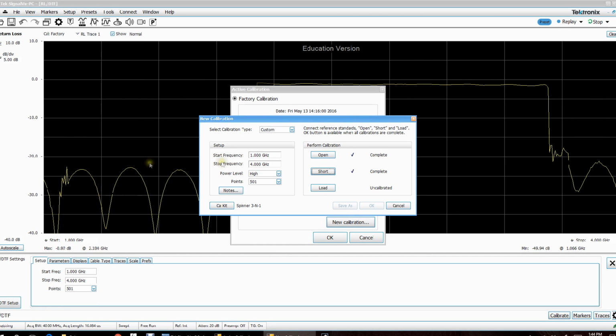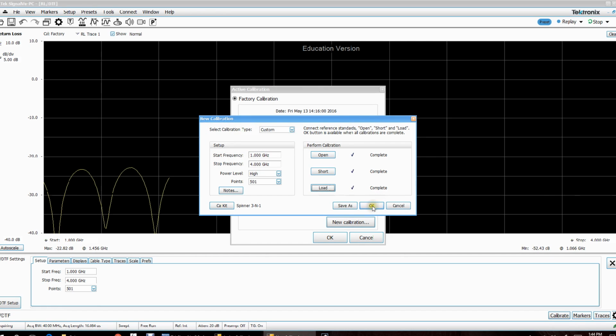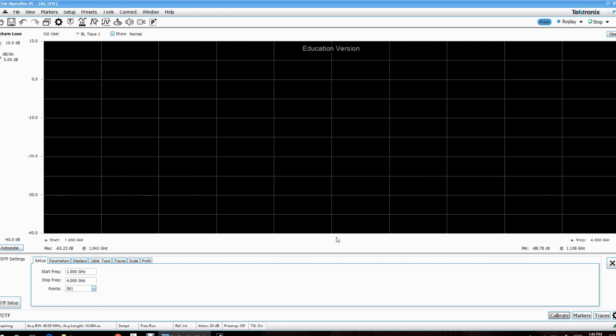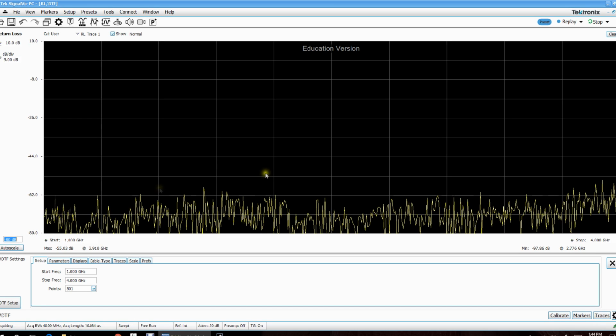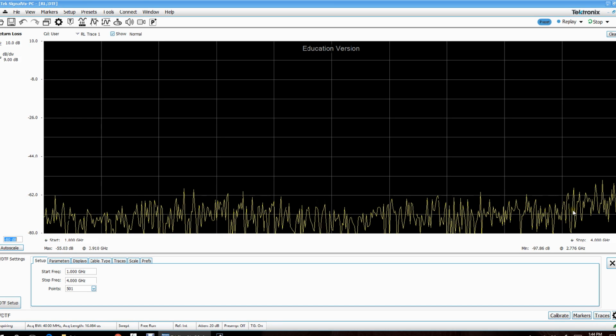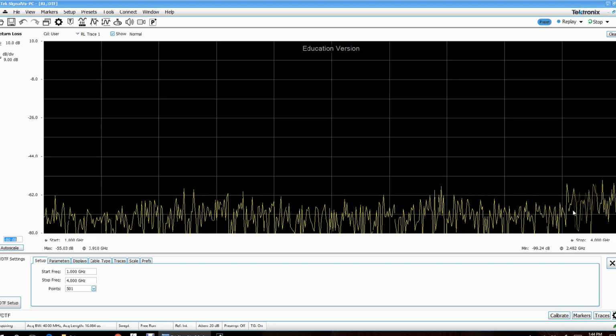And you can already see that we see the classic response over there. We're going to measure that. And it's going to look good once it's done. There it is. There is our calibration. Now it's applied and it's sitting below -40 because I'm terminating it with a load. So if I go, let's say -80, I should be able to see it. There it is. So we are sitting really low, below -62 dB return loss. So we have a pretty good calibration.